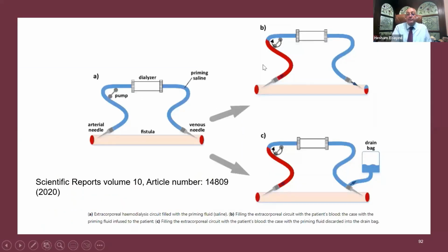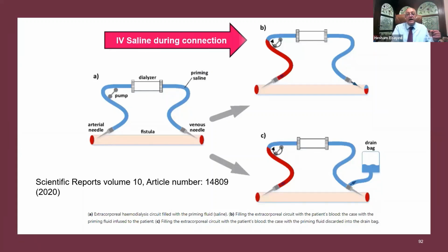That's why in some patients you can find that pushing saline at the start of the dialysis, meaning that once the patient is connected, you would not wait until the blood reaches the dialyzer and push the saline outside, but here you can push by a bag or other means so that the volume drawn from the blood is replaced by saline. So these are some of the measures to combat intradialytic hypotension at the start or the early phase of the hemodialysis session.